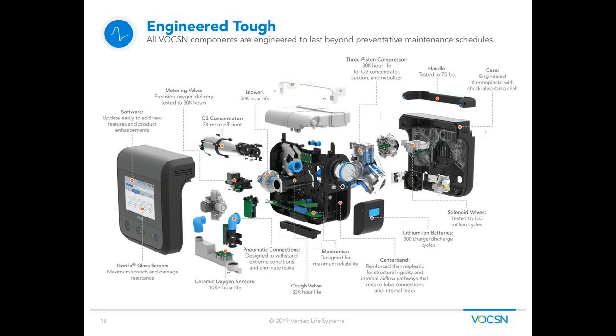With VOCSN, you can see here we have a three-piston compressor. It runs a lot slower, creates a lot less heat and wear and tear. It also creates a lot less noise, but because it has those three pistons, it can provide that consistent high flow. So we like to say VOCSN is engineered tough, and that it's going to last well beyond the typical preventative maintenance schedules you're used to for your ventilators today.